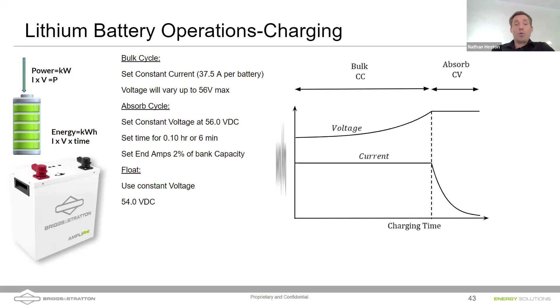And what happens is that the current was initially constant. And then when you hold it at 56 volts, as that battery goes from 95 to 100% state of charge, the current drops off slowly. And then you get a fully charged battery. So by the time you end the constant current bulk section of the charge, you're really at about 95% state of charge. And then for that last 0.1 hour, or 6 minutes, that's the constant voltage section. And that's where a lot of that balancing occurs. So do keep in mind that you do want to go through the occasional absorb cycle.